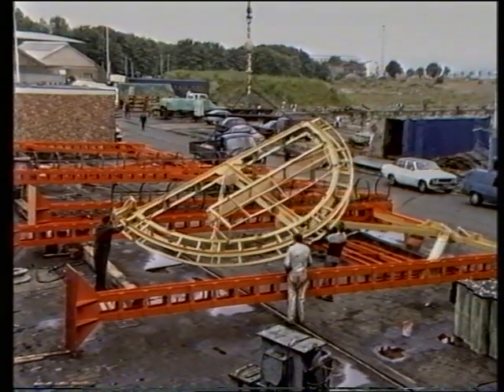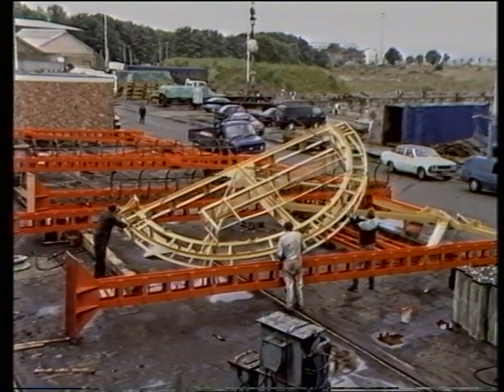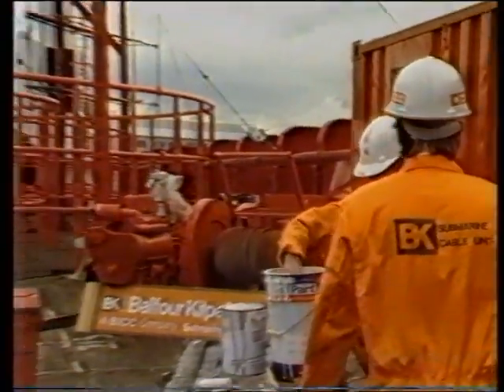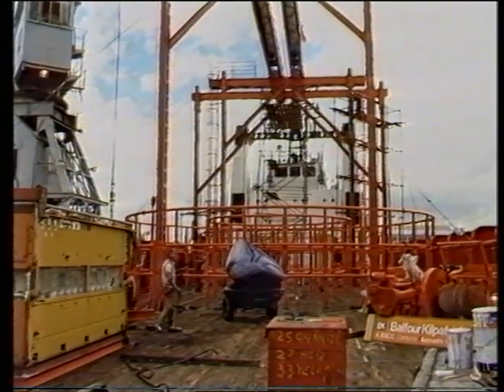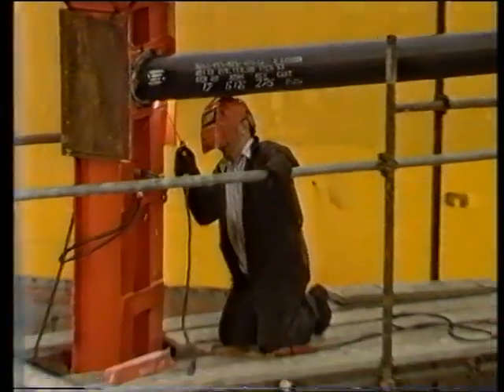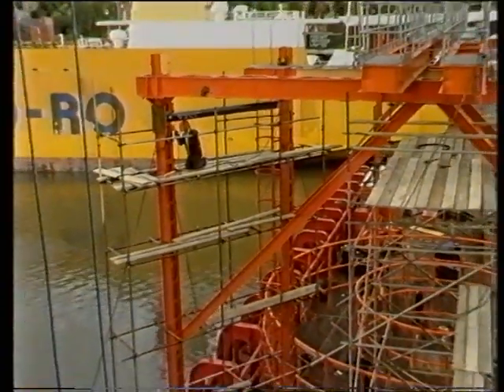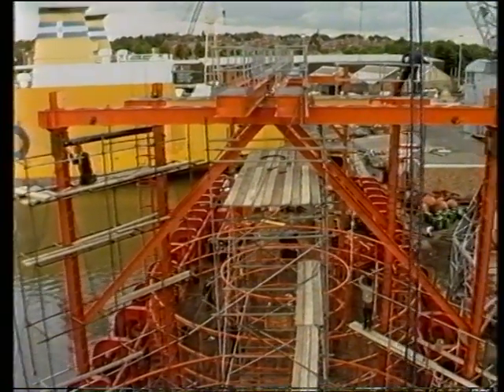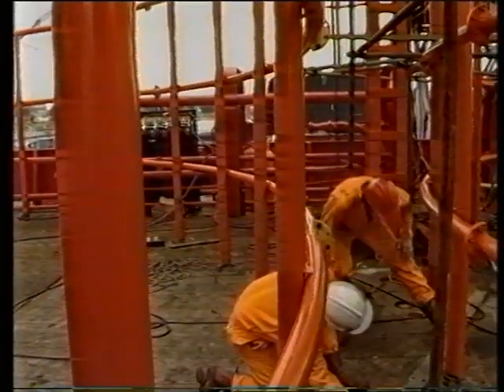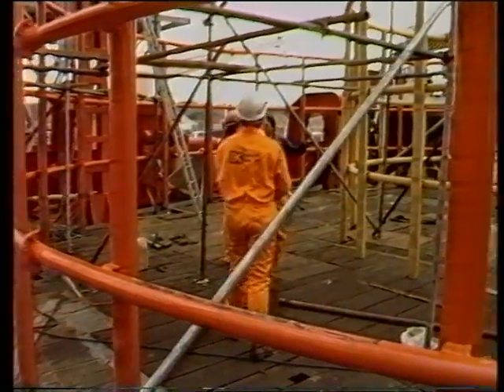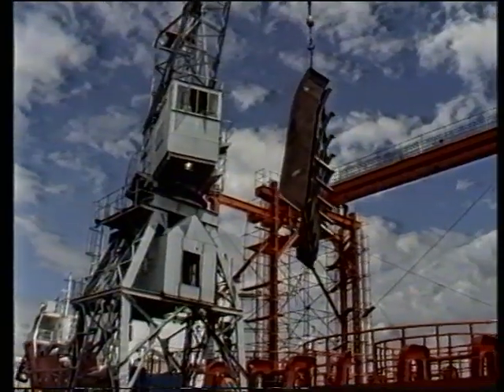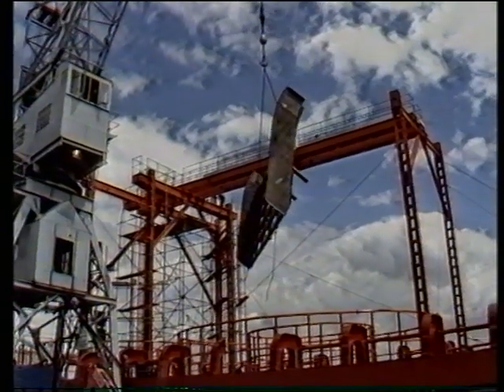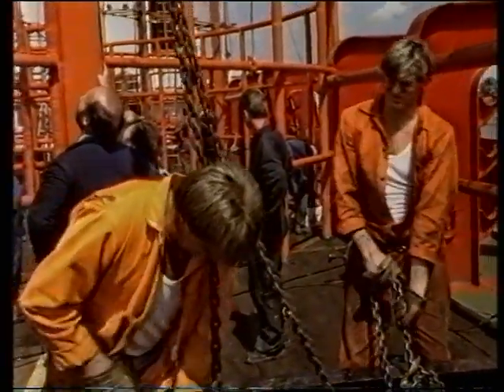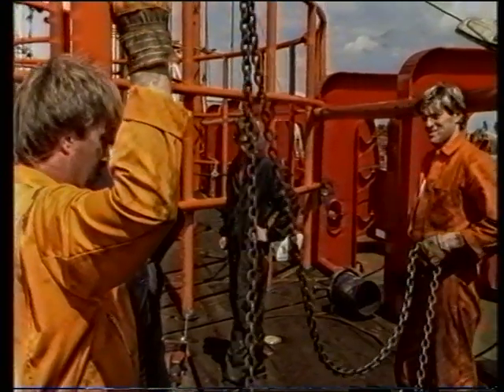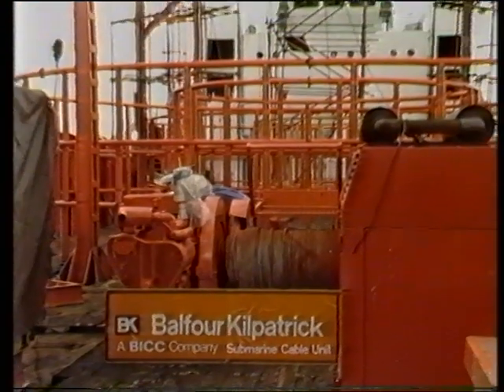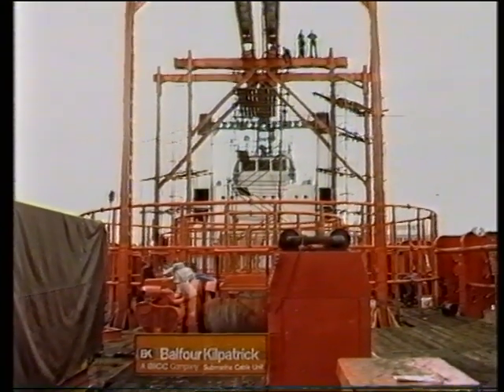Before she arrives, a huge array of metalwork has been made on the quayside in just 16 days, including 12-metre high cable handling equipment and 2 giant storage tanks for holding the 1,200 tons of cable. Painstakingly and skillfully, the structure is put in place on board the Star Hercules to make a series of goalpost fixtures on which the specialised gear for the cable installation will be fixed. All of this work has one purpose: to enable the cable laying operation to be as smooth and professional as possible. And that's why SWEB selected Balfour Kilpatrick, because of their long experience of this kind of work, their high reputation, and a very successful cable laying operation in the Scillies 3 years earlier. Under their guidance, the Star Hercules will be transformed into the perfect vessel for the job.